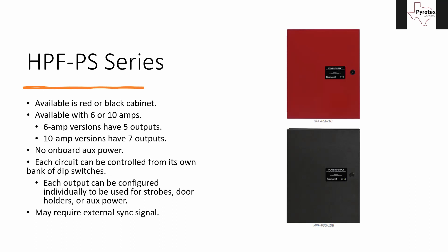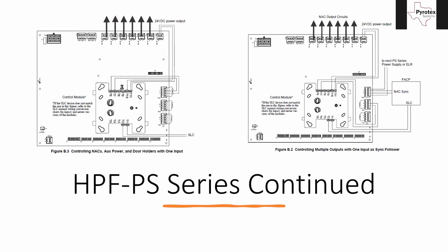The same note applies — it may require an external sync signal based on the same premises as before. If it's one standalone panel controlling all the NACs, you're not going to need any kind of sync signal. If you have multiple sources for your strobe circuits, it is going to require a sync signal because we'll need to sync the panels together. I haven't gotten to see one of these in person yet and they don't have real pictures out; these images came out of the manual posted on the website.